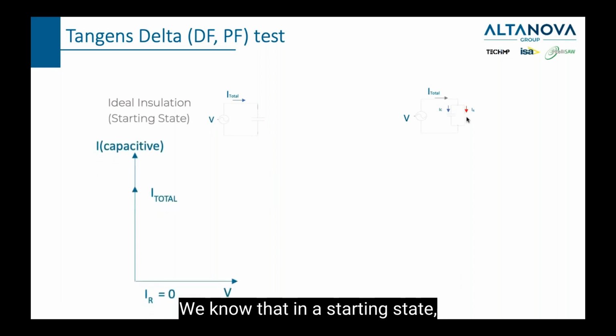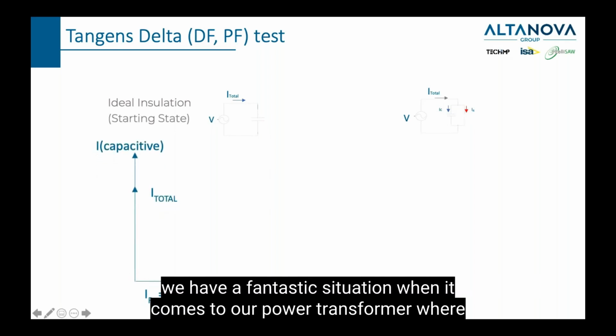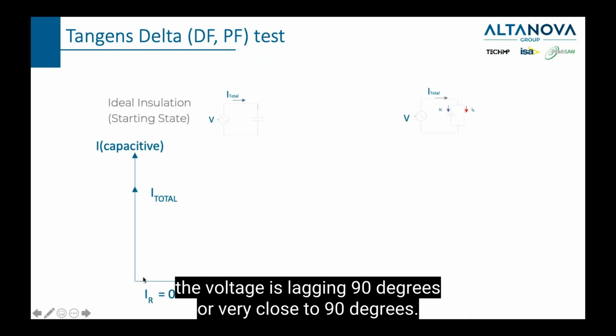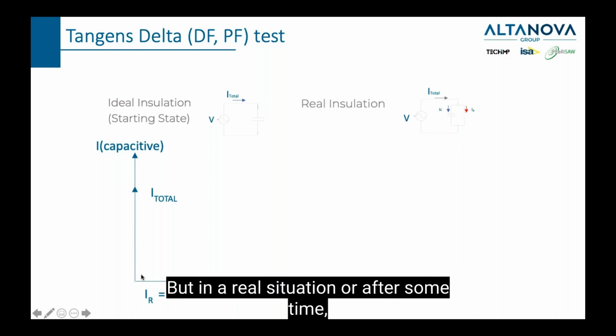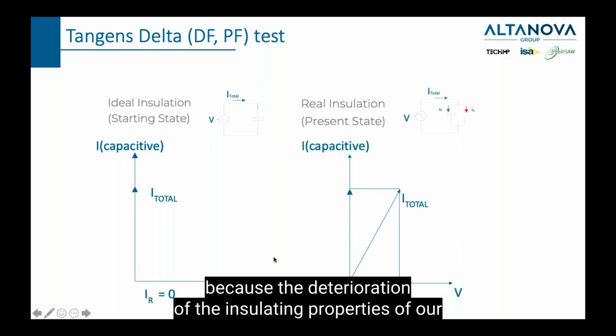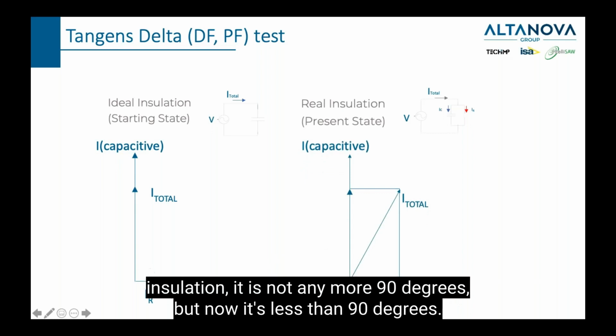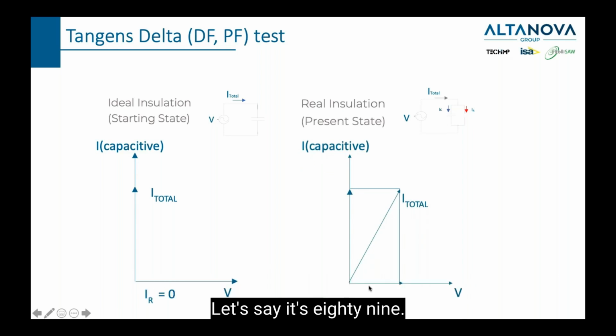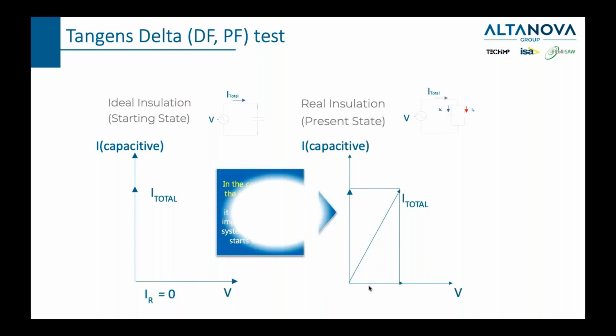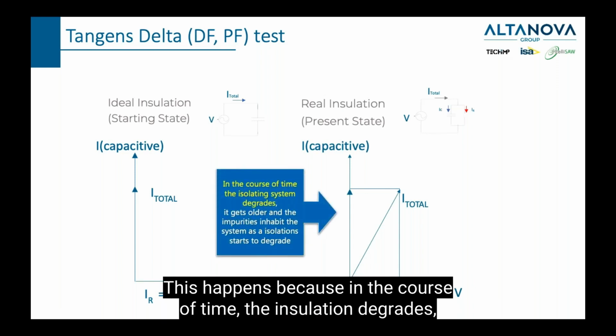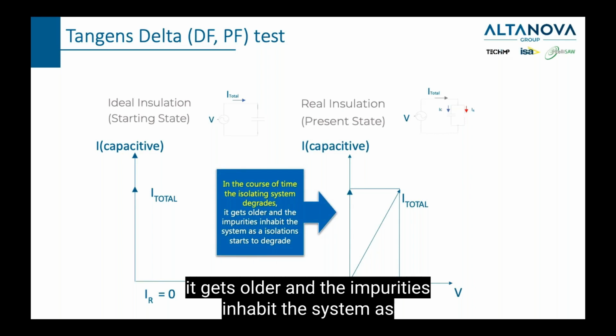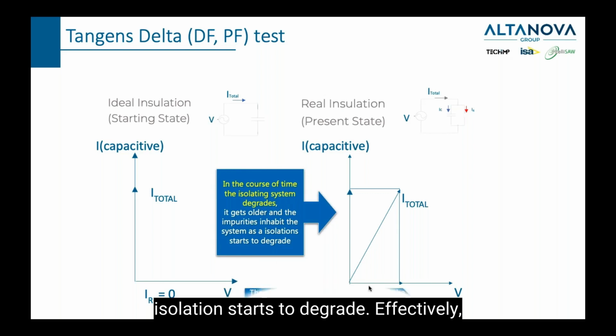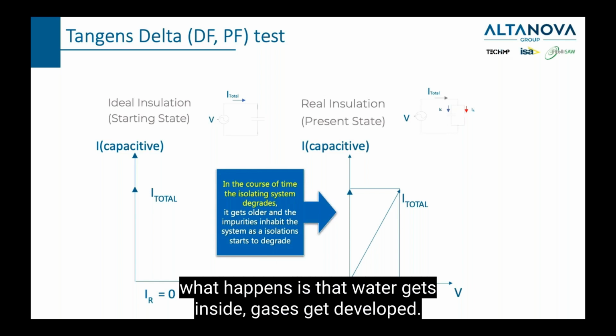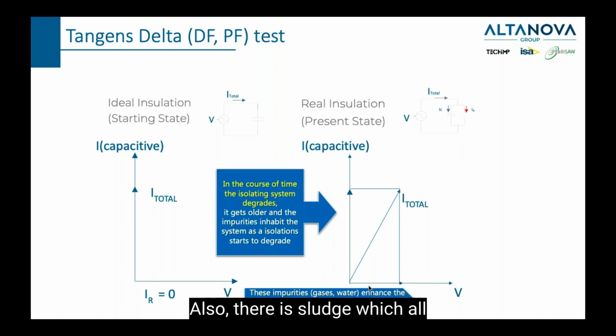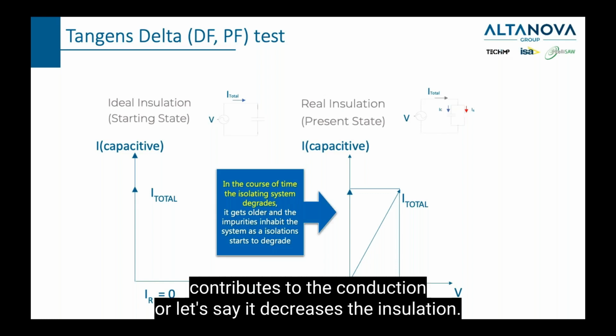We know that in a starting state, we have a fantastic situation when it comes to our power transformer, where the voltage is lagging 90 degrees or very close to 90 degrees. But in a real situation or after some time, because of the deterioration of the insulating properties of our insulation, it is not anymore 90 degrees, but now it's less than 90 degrees. Let's say it's 89. 1 degree makes a lot of difference. This happens because in the course of time, the insulation degrades. It gets older and the impurities inhabit the system as the insulation starts to degrade. Effectively, what happens is that water gets inside, gases get developed. Also, there is sludge, which all contributes to the conduction, or let's say it decreases the insulation.